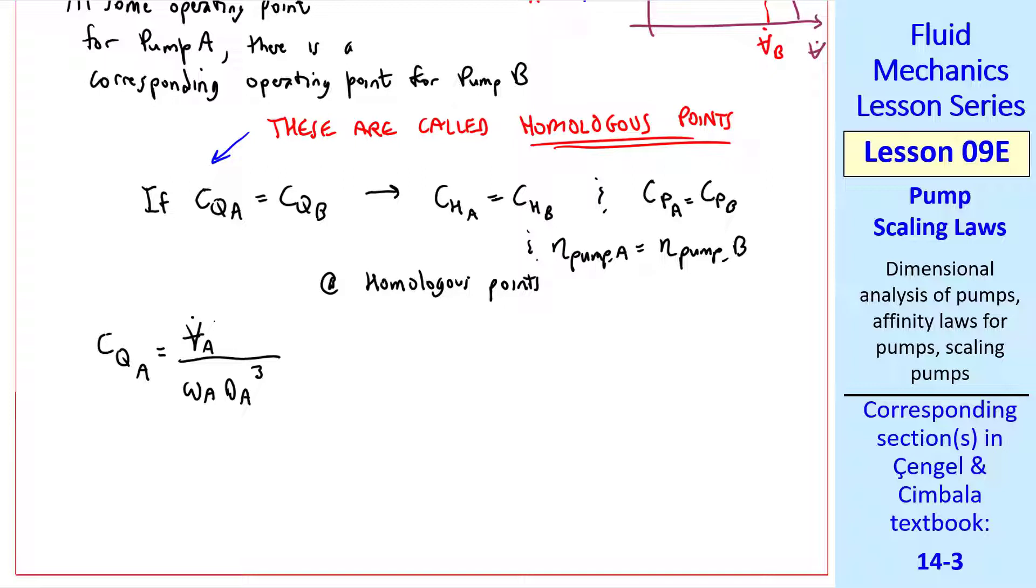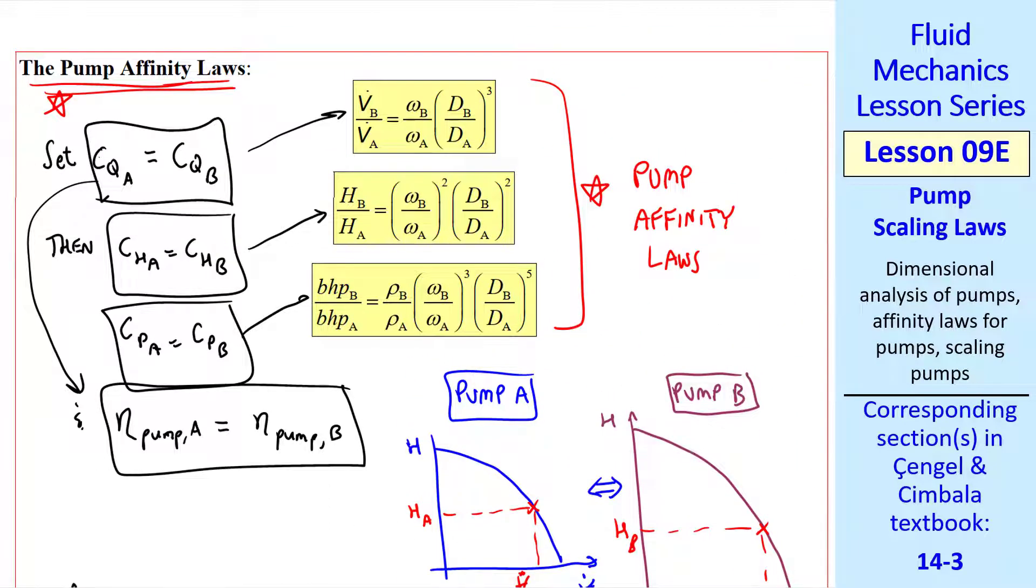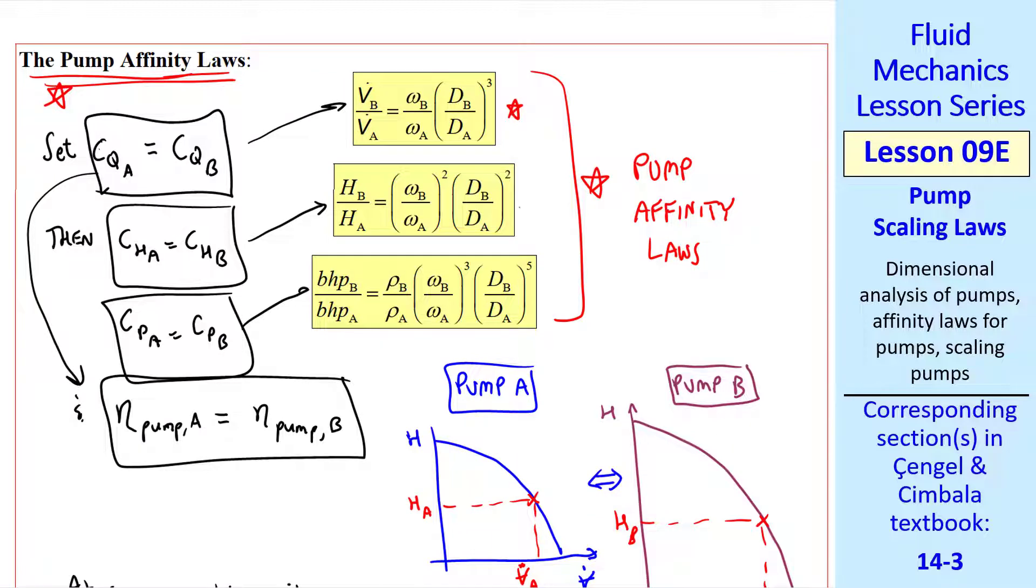Let's do a little bit of algebra. CQA is V dot A over omega A DA cubed, and at homologous points this is also equal to V dot B over omega B DB cubed, which we write as V dot B over V dot A equal omega B over omega A DB over DA cubed. This is our first affinity law. When I scroll up, you can see that this is this equation. In an exactly similar way, we get these two equations. If we put an exponent one on the omega B over omega A term in the first equation, we see that we have an exponent of one, two, and three on the ratio of omegas, which is the angular velocity rotation rate of the pumps.